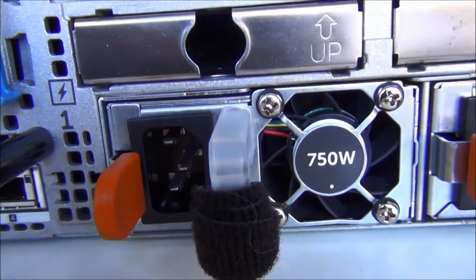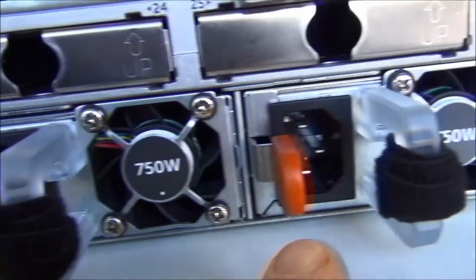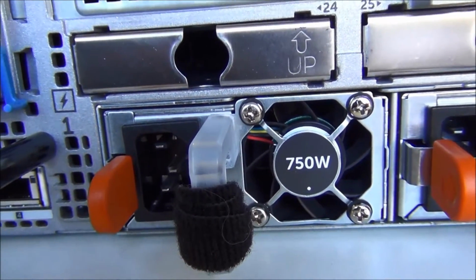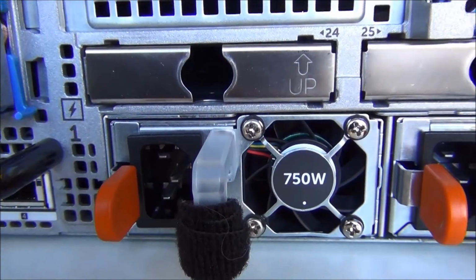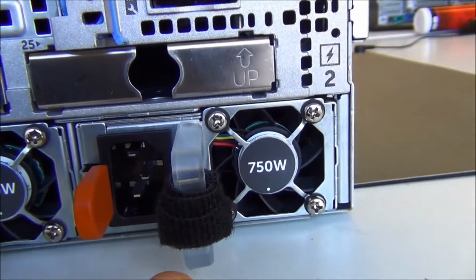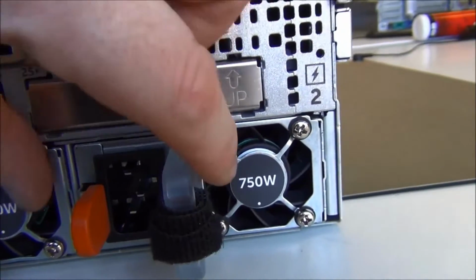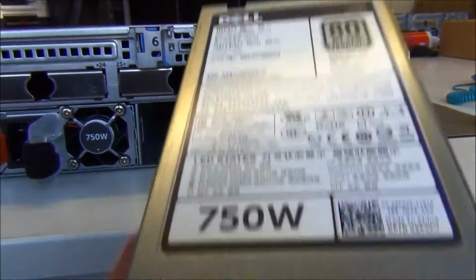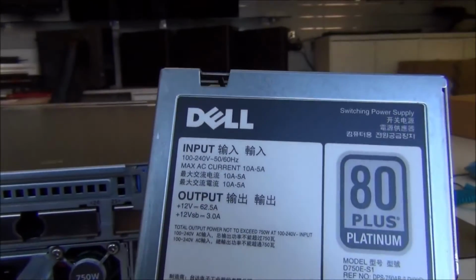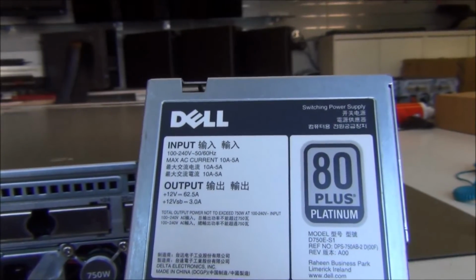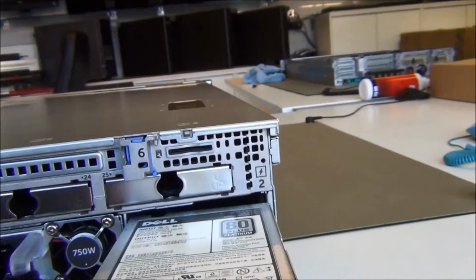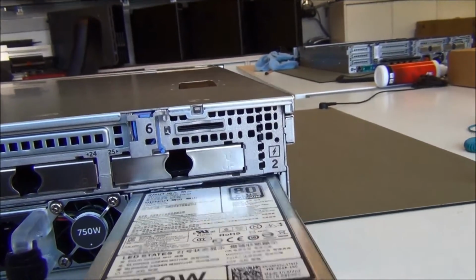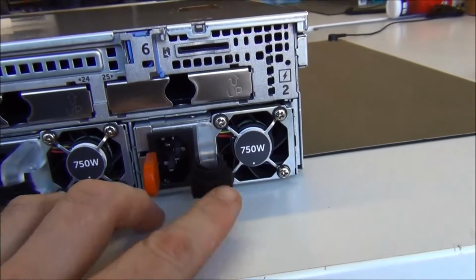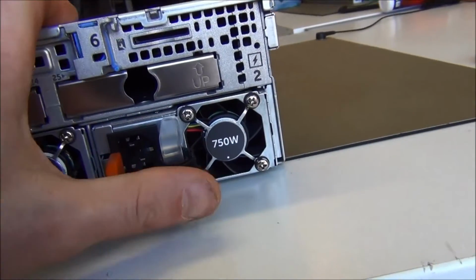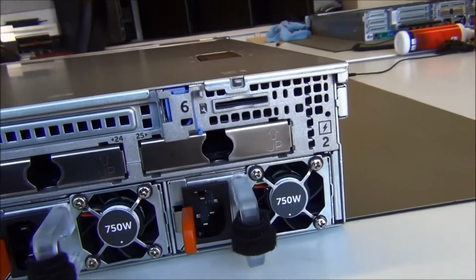Here we can see we've got two 750 watt power supplies. And they, of course, offer redundancy just in case you need to swap one out. They're both also hot plug and so come out as easily as that. As you can see, 750 watt. It's one of the 80 Plus Platinum range. And fitting them back in, it's just a click away.